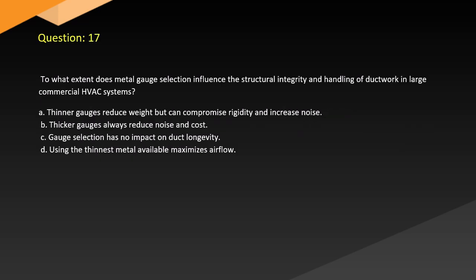Question 17. To what extent does metal gauge selection influence the structural integrity and handling of ductwork in large commercial HVAC systems? A. Thinner gauges reduce weight but can compromise rigidity and increase noise. B. Thicker gauges always reduce noise and cost. C. Gauge selection has no impact on duct longevity. D. Using the thinnest metal available maximizes airflow.